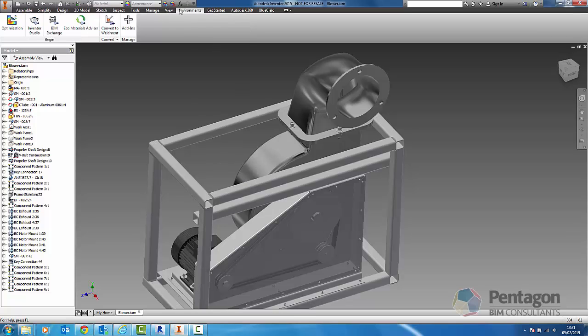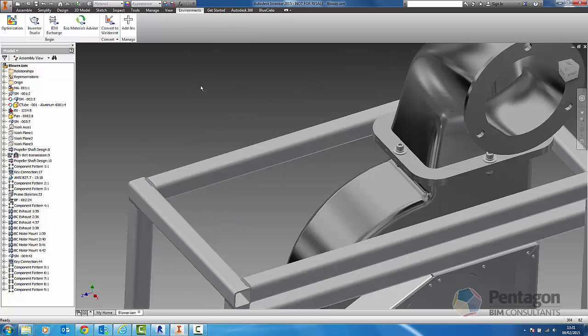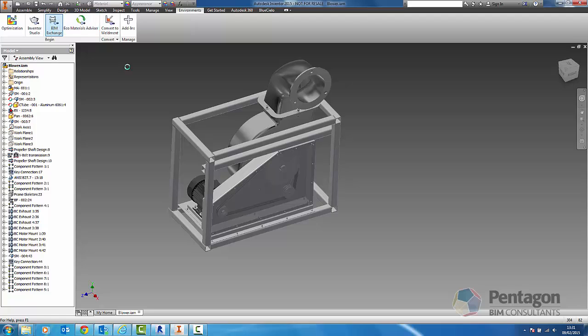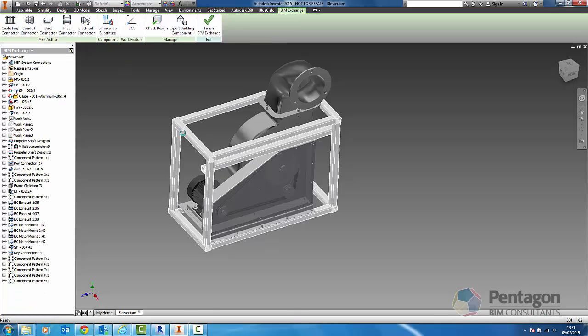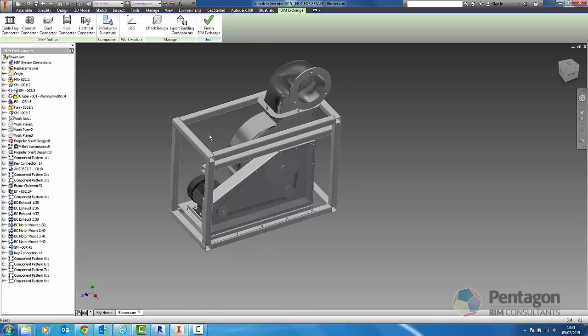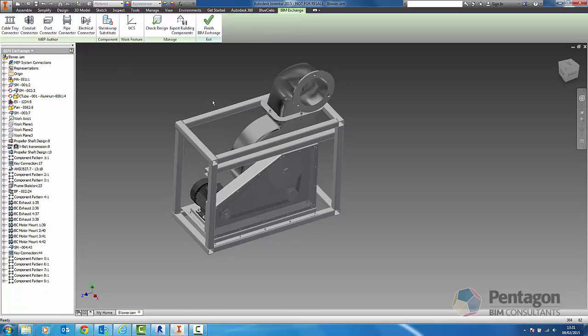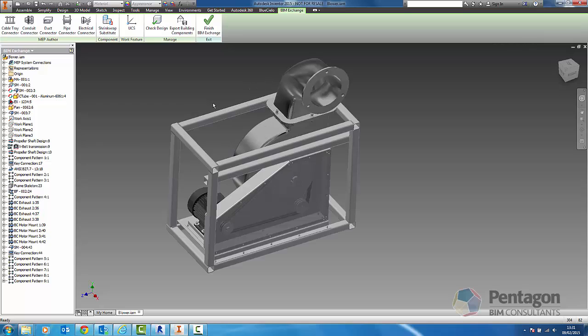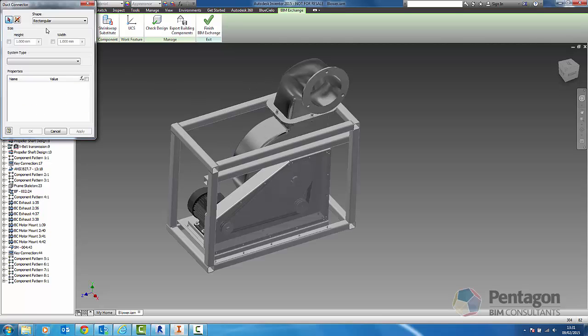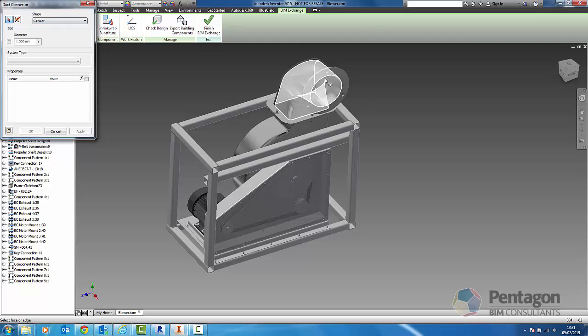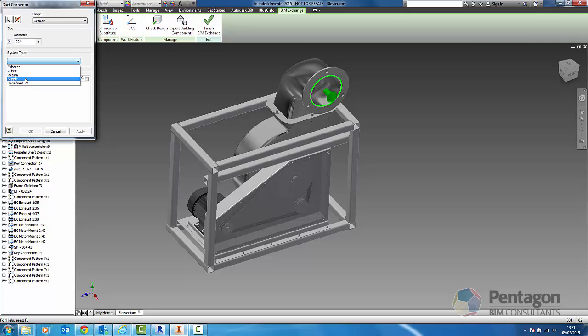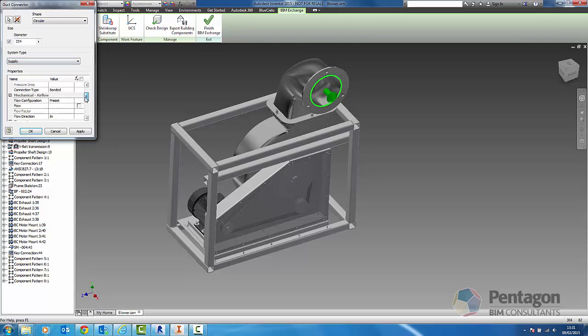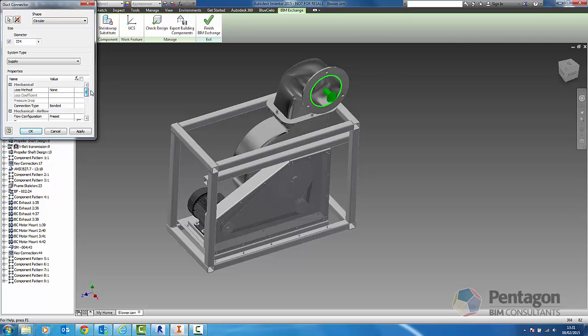In our environment, we actually have a BIM exchange tool. We can simply go to our BIM exchange tool and we can look at our components in here. The first thing we're going to do is add connectors and we're going to add a circular connector at key parts. You can note the direction as well and we're going to put in the actual diameter and specify it. We can say whether that's a supply or return and it looks at the various mechanical properties to physically add into the model itself.